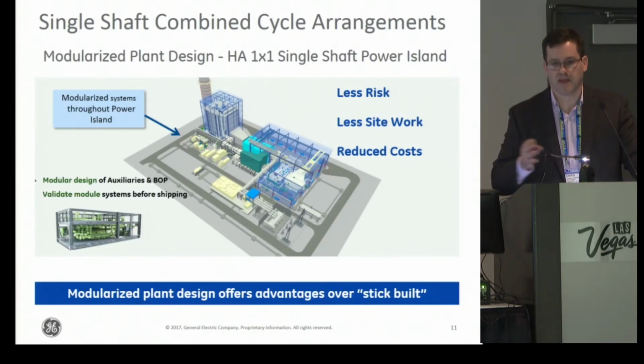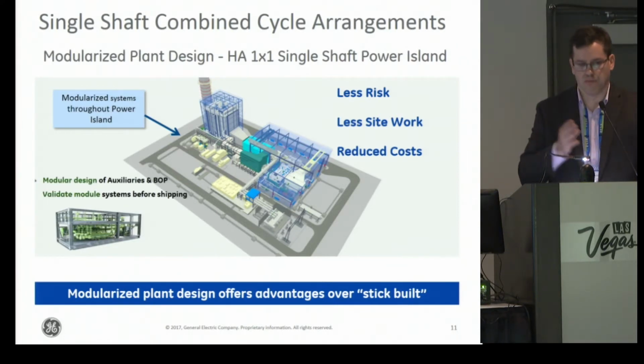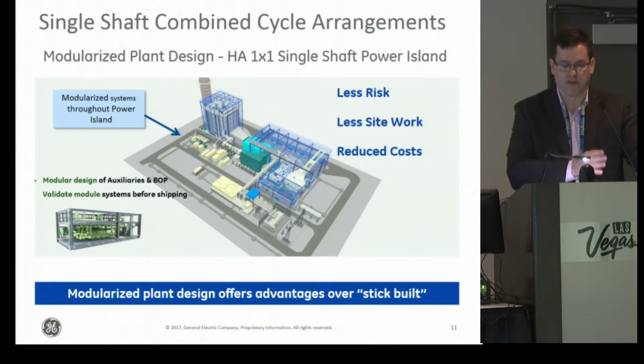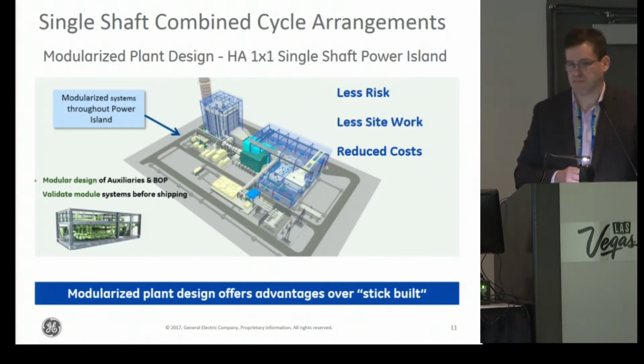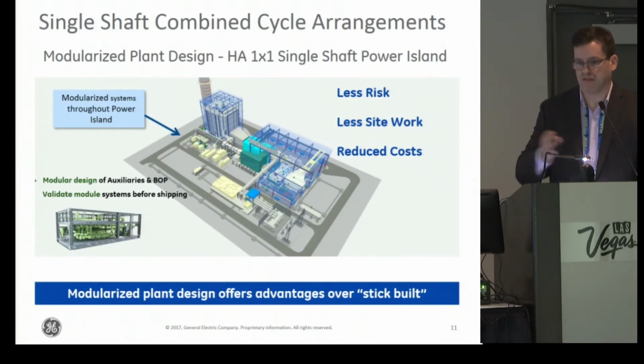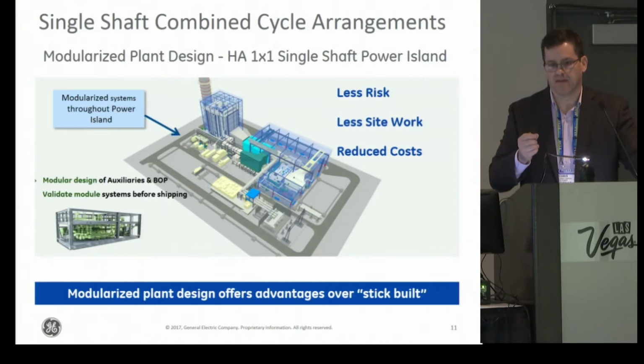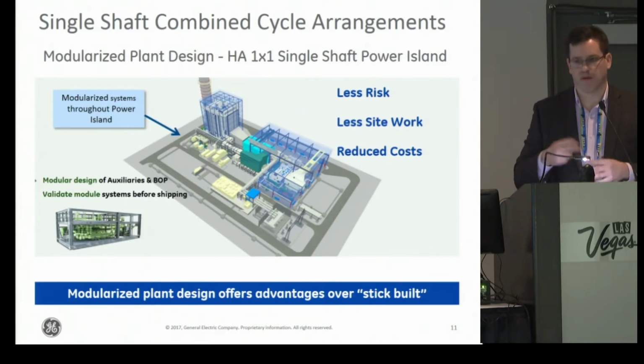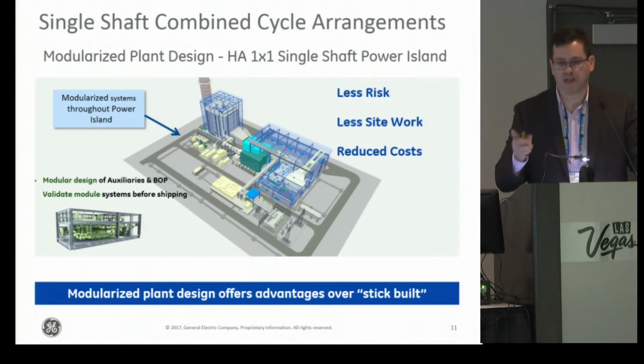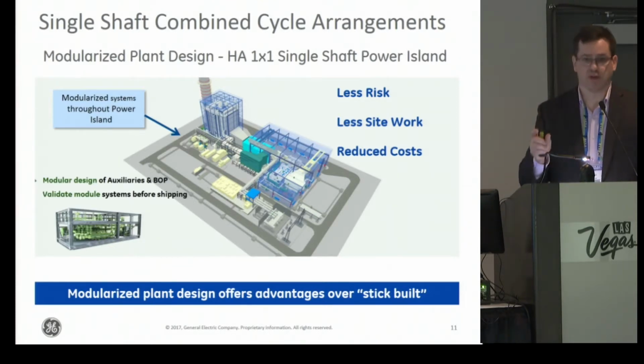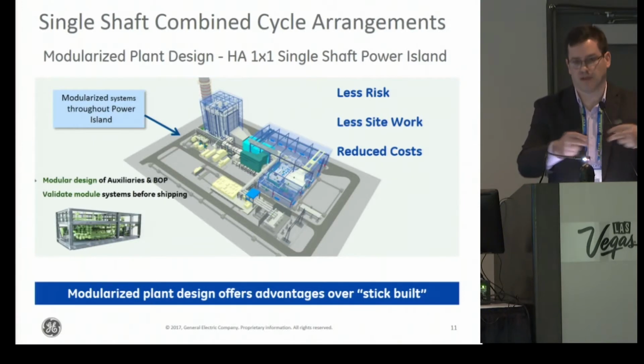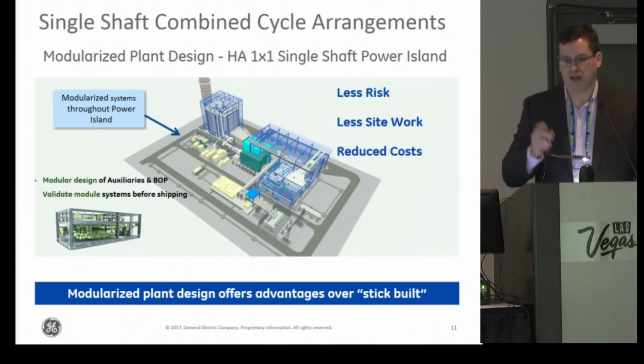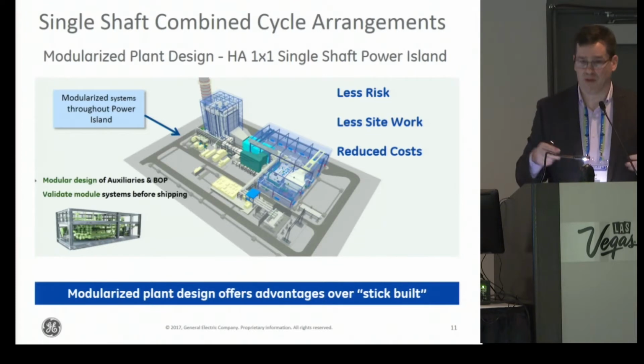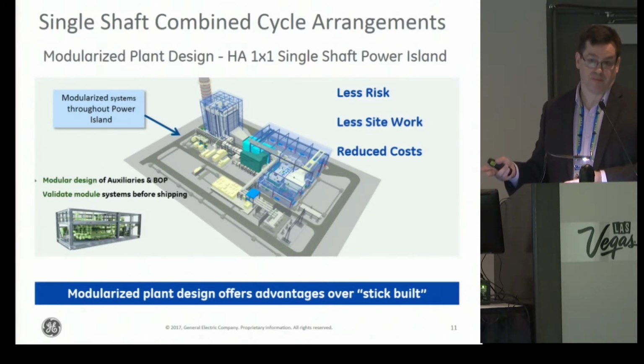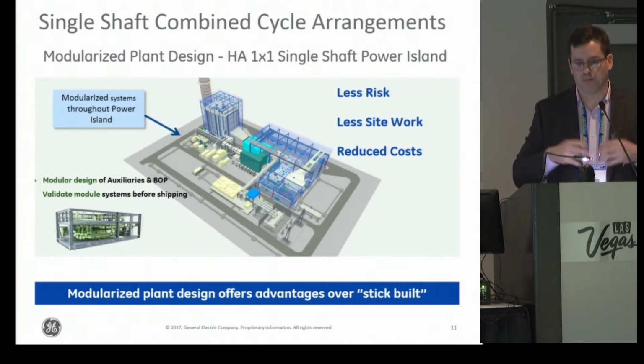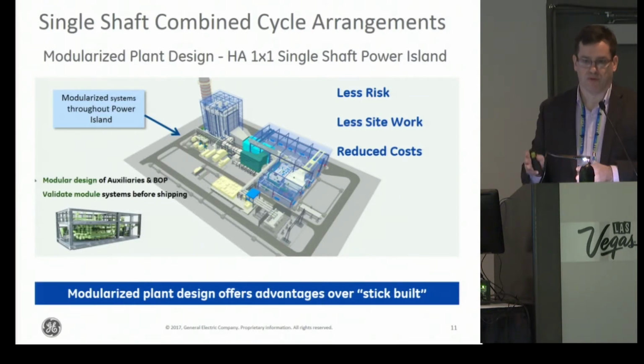And that's one big thing about looking at a multi-shaft as opposed to multiple single shafts on a particular site. If you have a multi-shaft combined cycle, say a 2x1 or a 3x1, you have a single point failure on that plant, which is that steam turbine and that steam turbine generator, and then the electrical hardware for that steam turbine generator. If you have a failure on any one of those pieces of equipment, you're probably not going to run the gas turbines in simple cycle. So there's places where that whole plant can be taken out due to a single point failure.